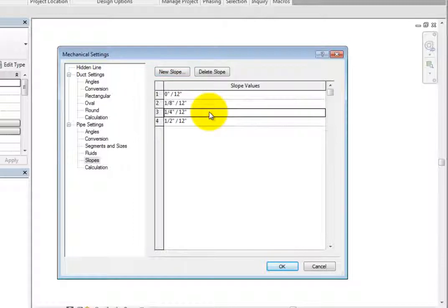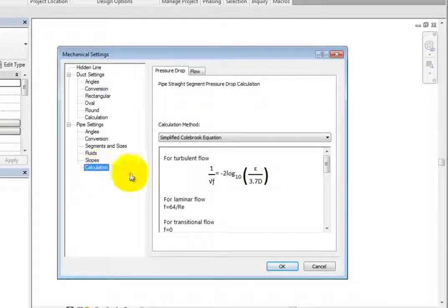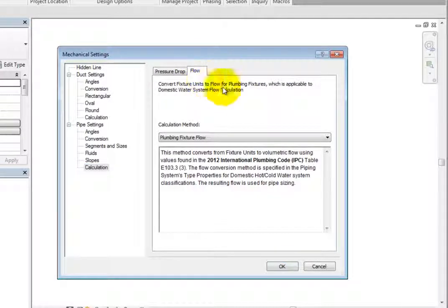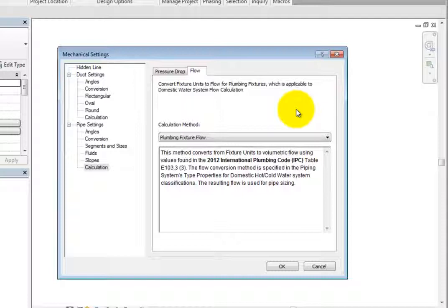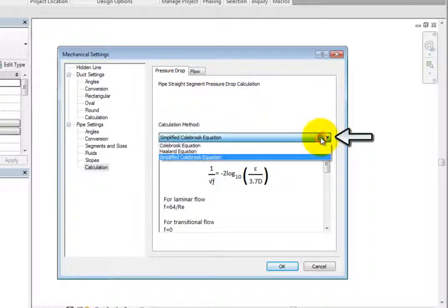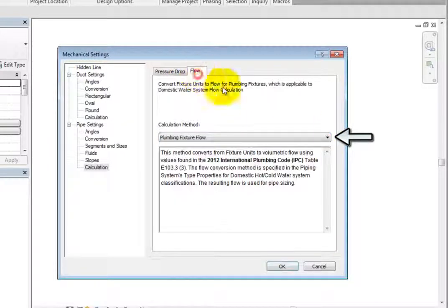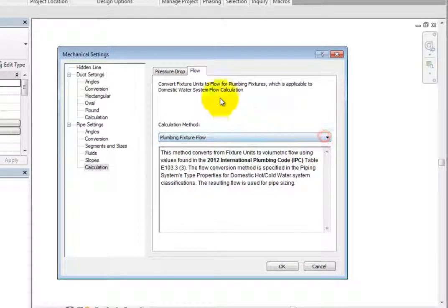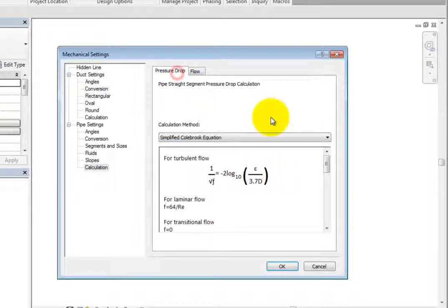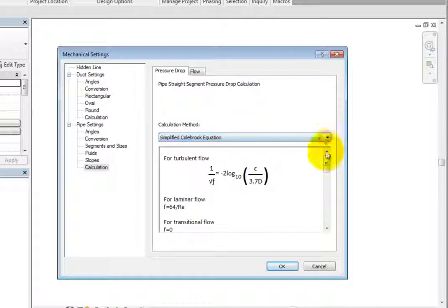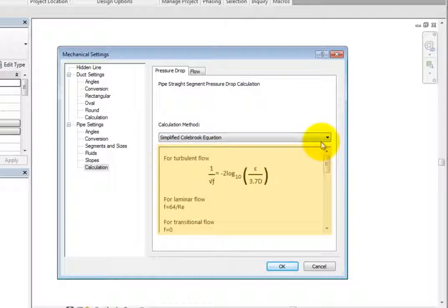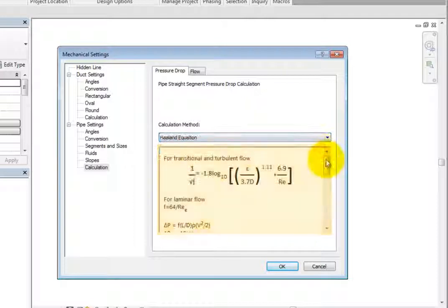Lastly, when you select Calculation, you can see the calculation method used for pipe straight segment pressure drop calculation on the Pressure Drop tab and how fixture units are converted to flow for plumbing fixtures on the Flow tab. On either tab, when you expand the calculation method drop down, you can choose the method you want to use. Third-party developers can create additional calculation methods and install them as add-ins. If you install one of these new methods, you can select it here in the calculation method drop-down. Below the drop-down, you can see the equation and the variables used to calculate the pressure drop.